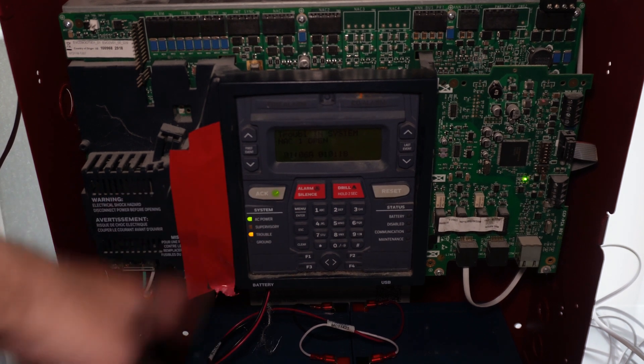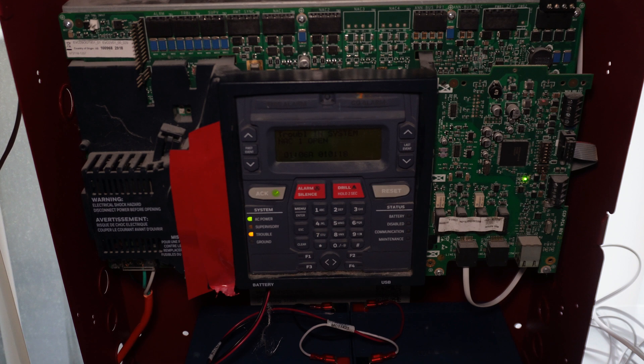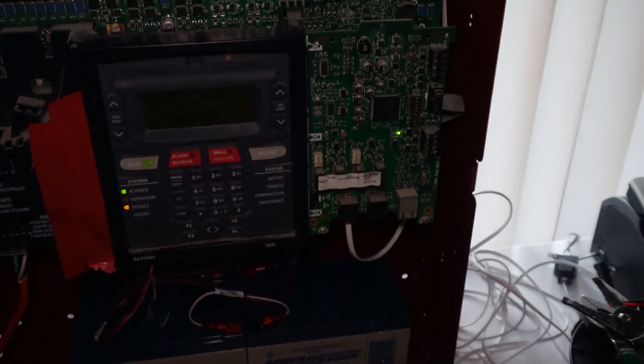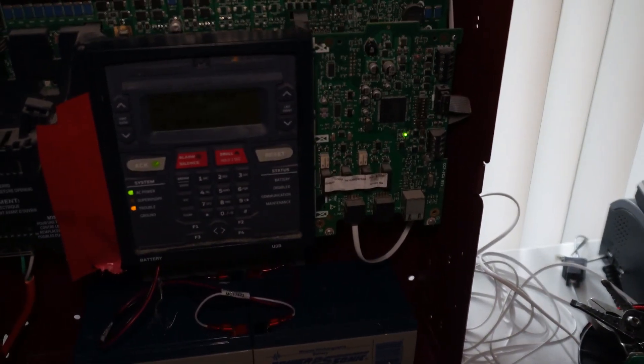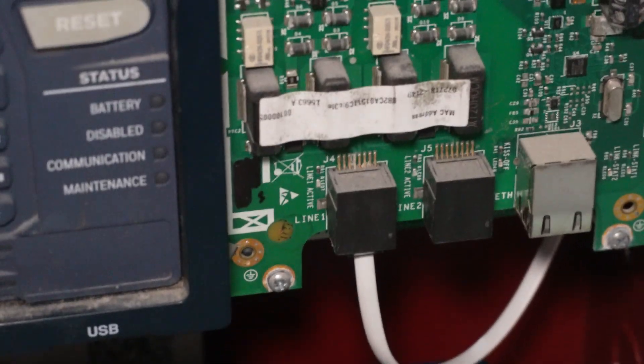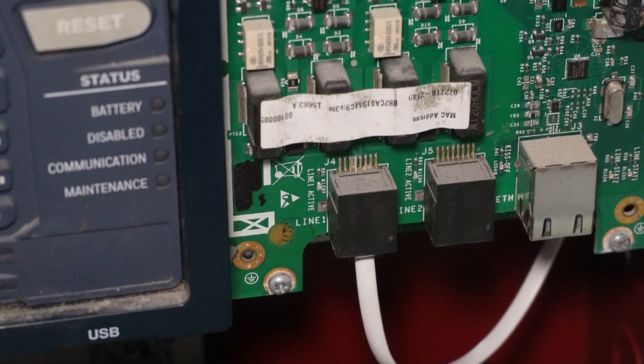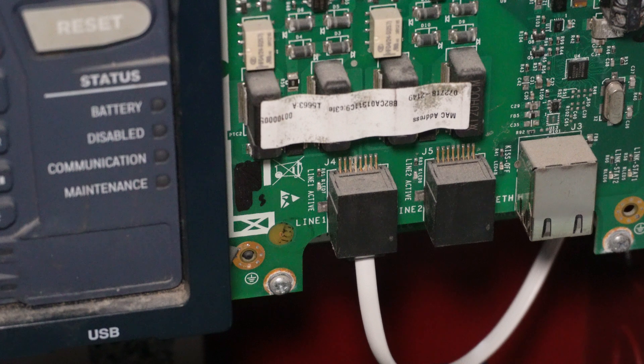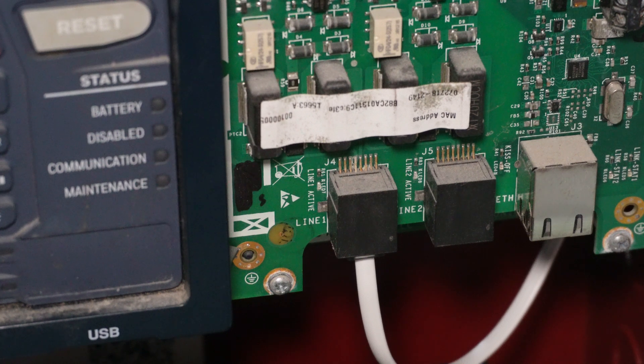And there you have it. But it's also going to communicate every trouble that comes up on the system too, like it's beeping at me right now about. But it appears that we have successfully gotten the communicator to work and is reporting to a central monitoring station. Let me also show you what I'm talking about when it periodically just opens the line for like a millisecond, just to make sure there's still voltage there. Because we did enable supervision earlier.